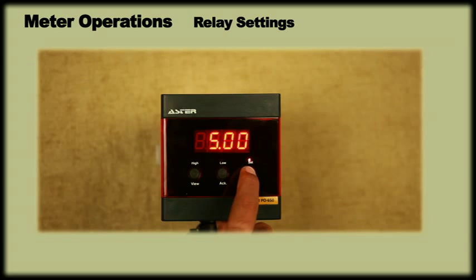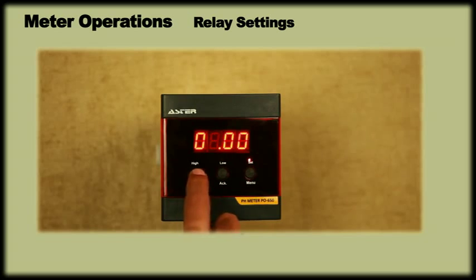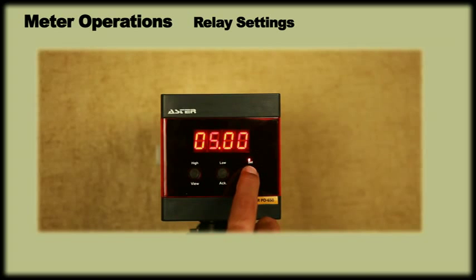By pressing menu, it will display a previously set low value. Using ACK key and view key, we can set the required low pH value. For example, let us set low pH value as 5 and press menu to enter. Always remember that the low set point should always be lower than the high set point, else the meter will show set error. Now the display will show hysteresis 2.